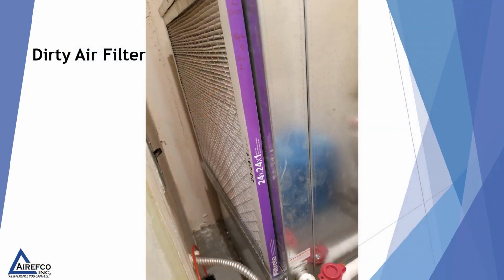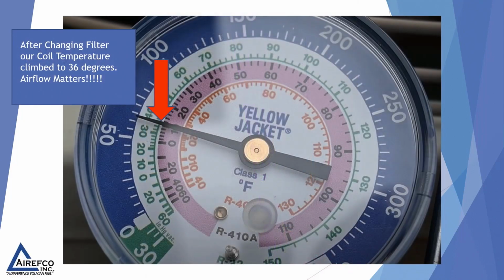So when the tech first got to this job, he noticed that he had a dirty air filter on the air handler. So when he got the low reading of a freezing coil on his gauges, he wanted to make sure that he had the proper airflow. So he changed the dirty air filter and put a new filter in the system. After changing the filter, our coil temperature climbed to 36 degrees.